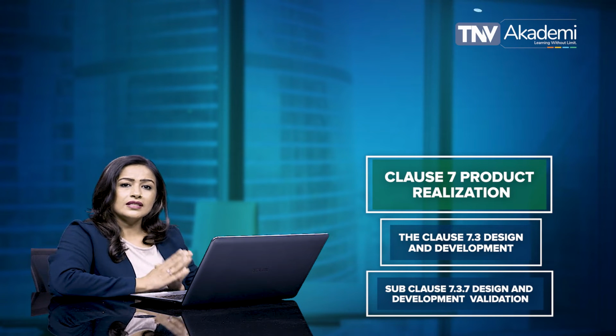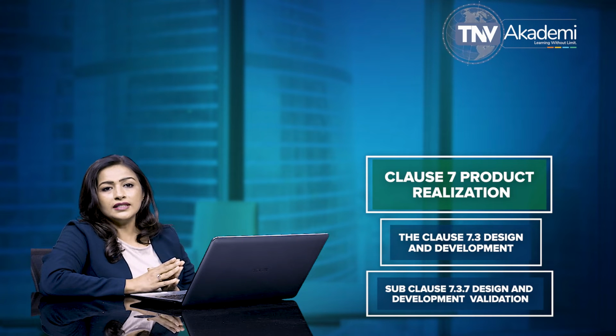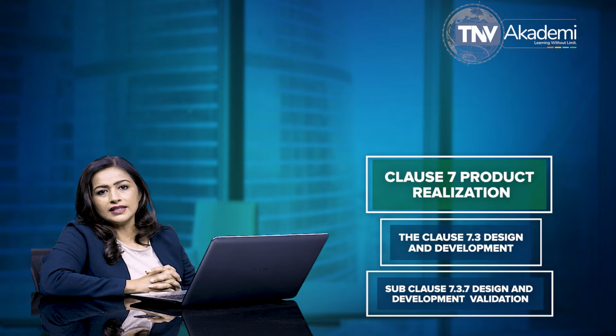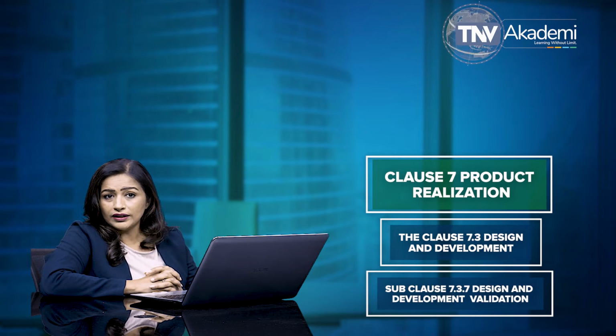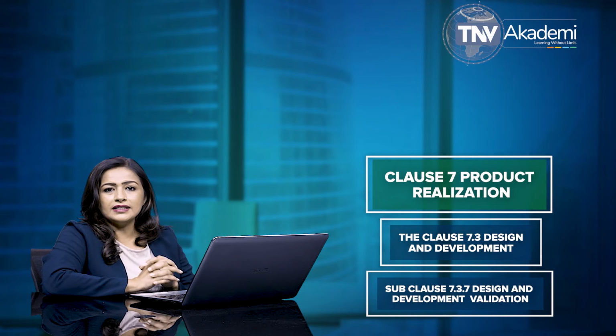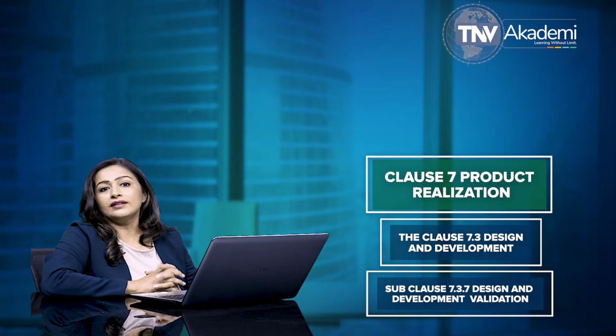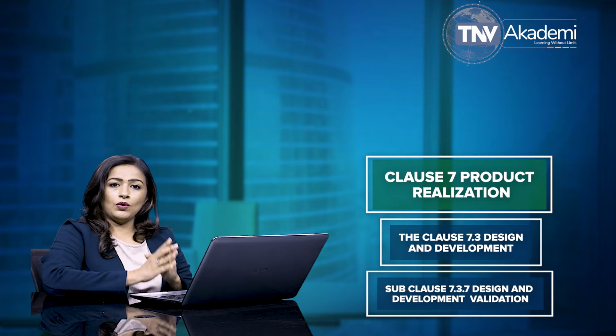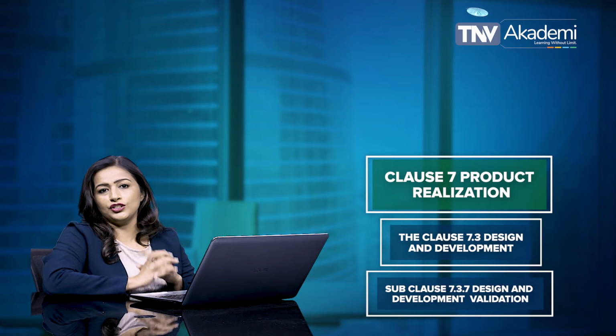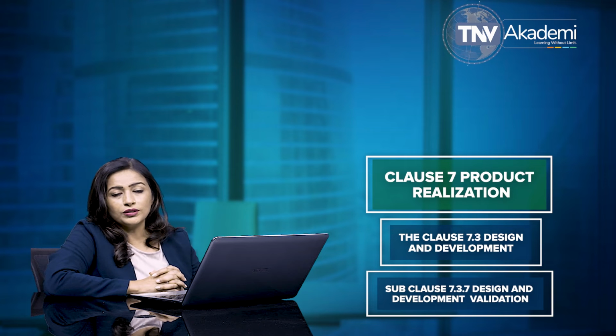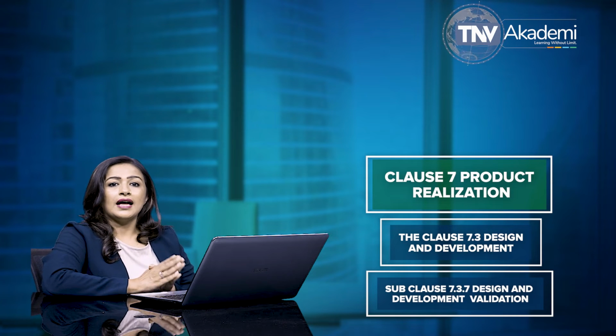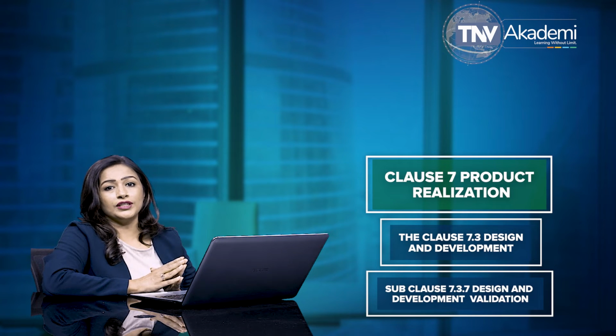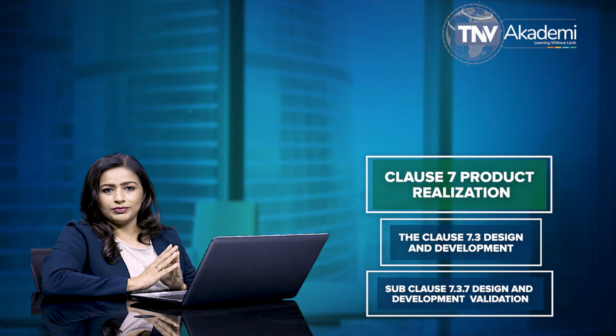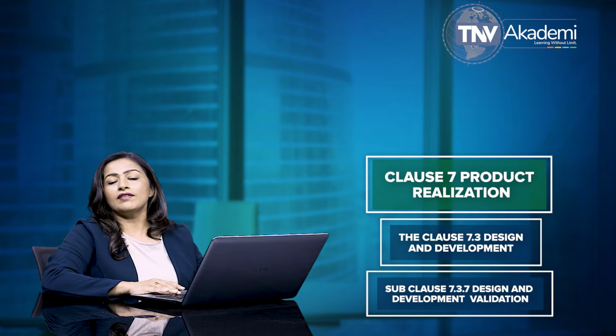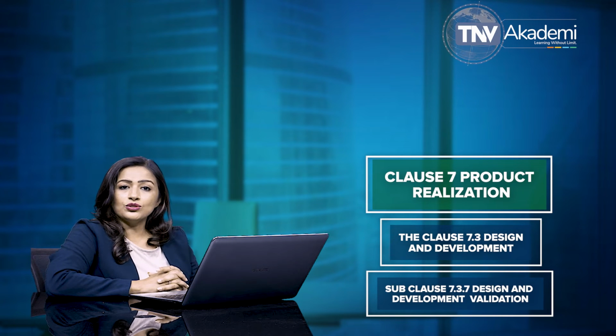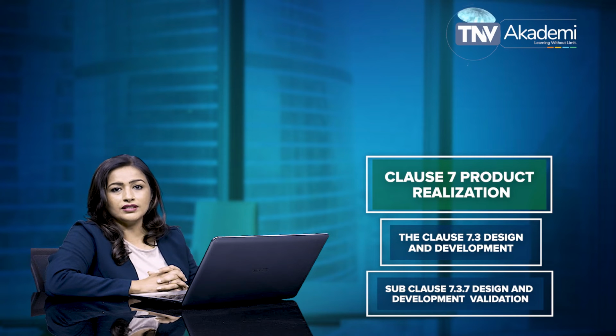According to this subclause, 7.3.7 of ISO 13485:2016, the design and development validation is required to be performed in accordance with planned and documented arrangements to ensure that the resulting product is capable of meeting the requirements for the specified application or intended use. The organization is required to document validation plans that include methods, acceptance criteria, and, as appropriate, statistical techniques with rationale for sample size. Subclause 7.3.7 states that design validation is required to be conducted on representative product.